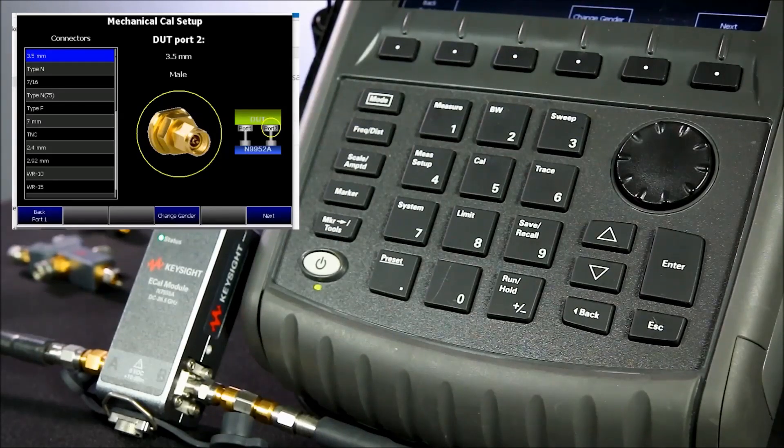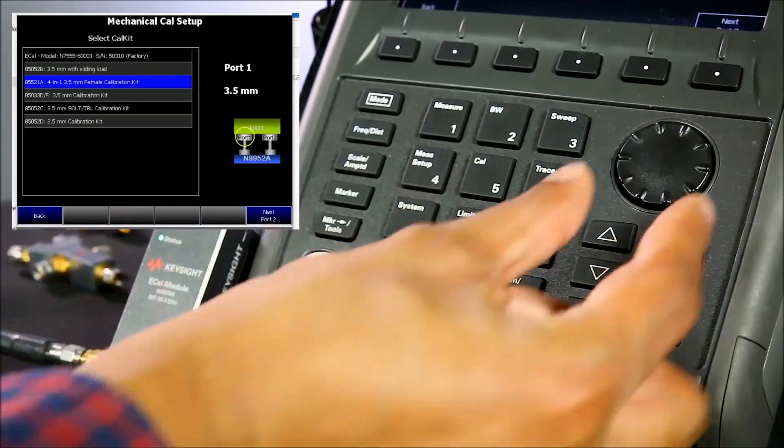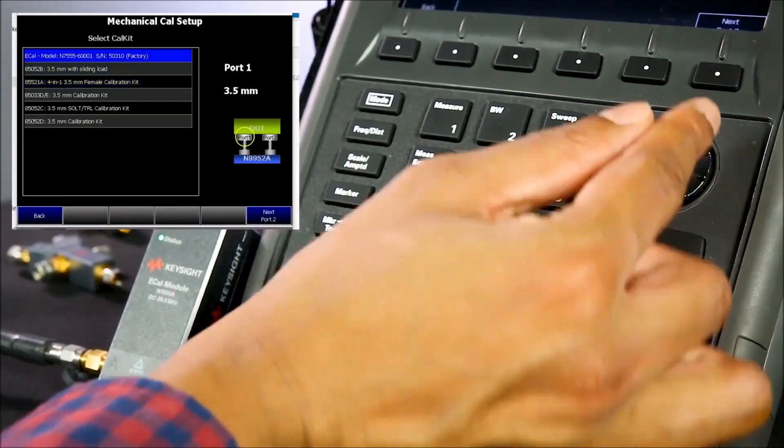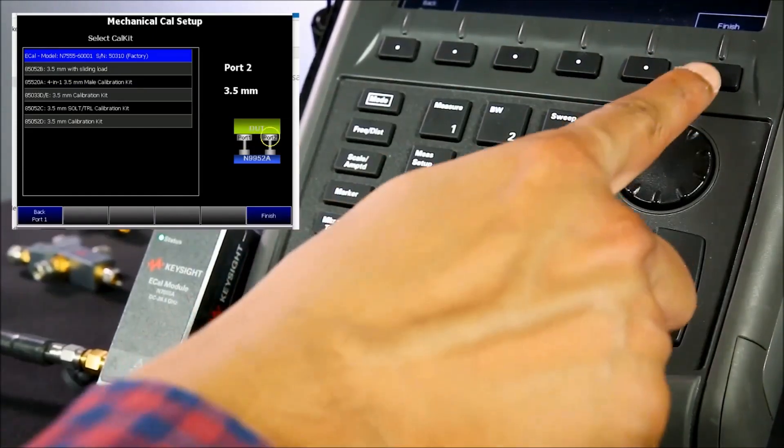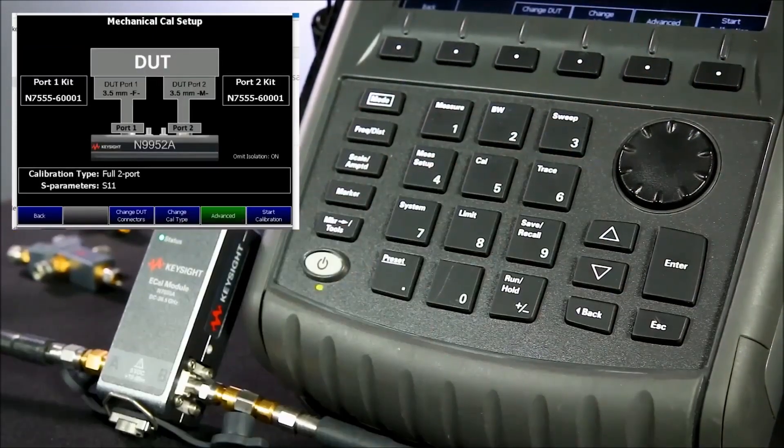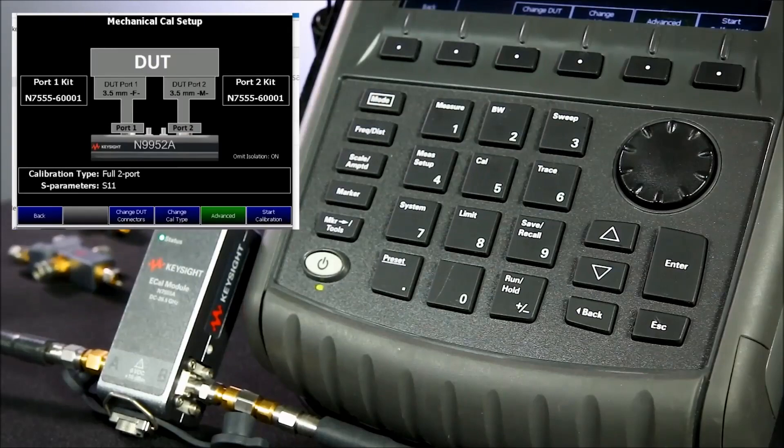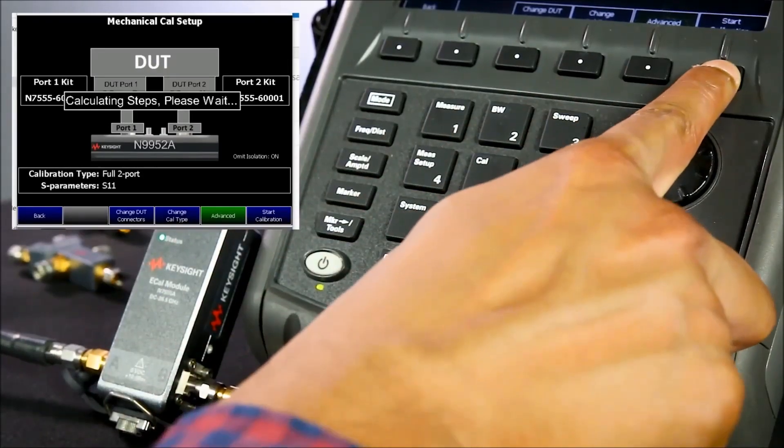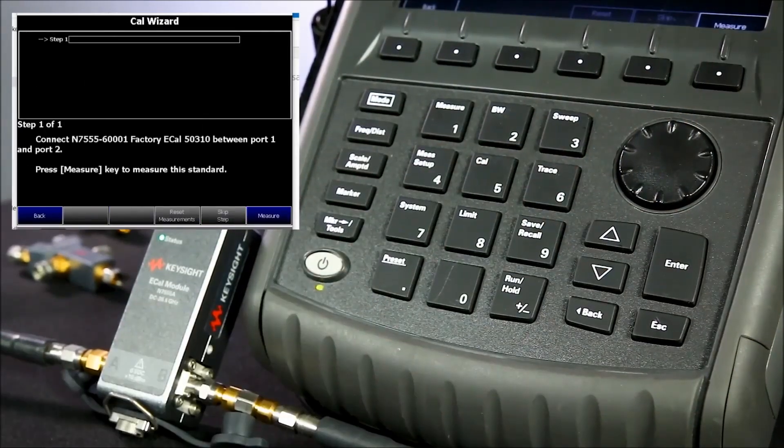FieldFox supports a variety of calibration kits. So finally, select the e-CAL module for port one and for port two. Notice the nice CAL setup display. My calibration is set up properly.